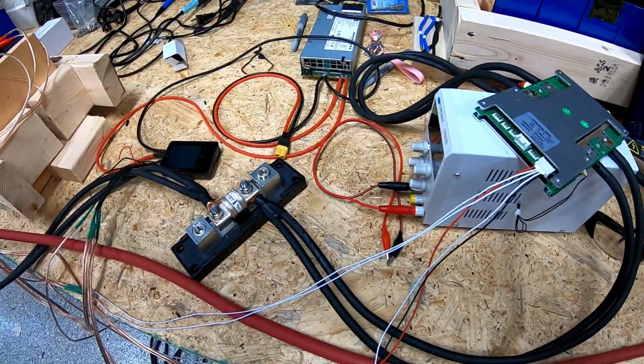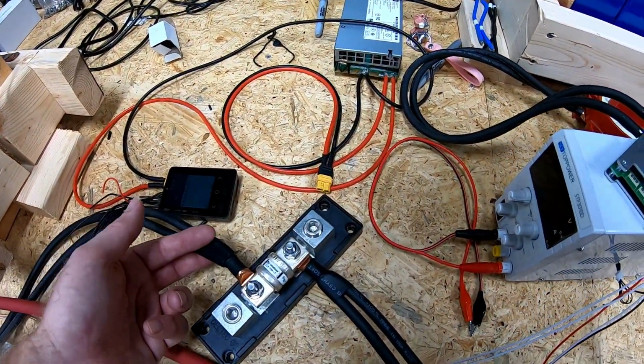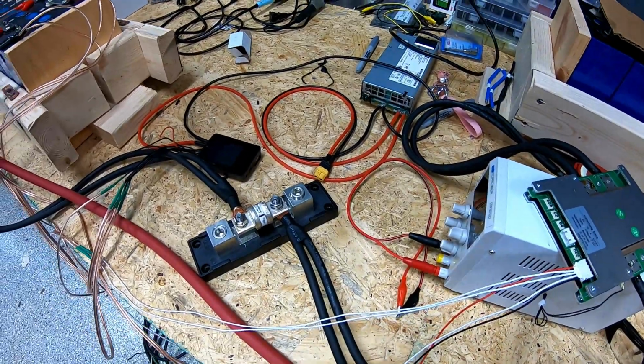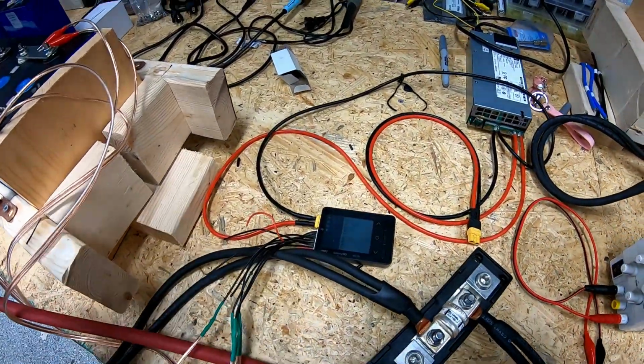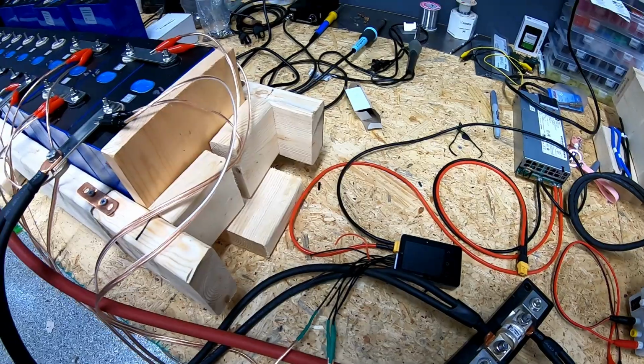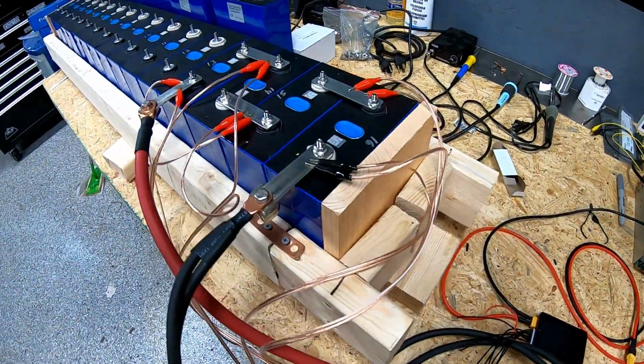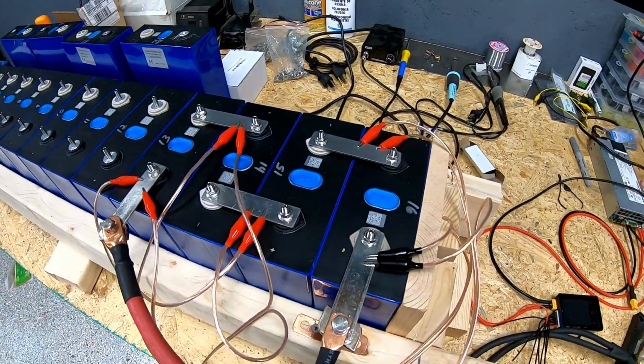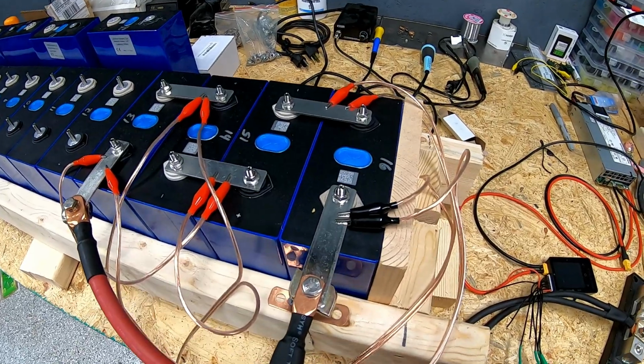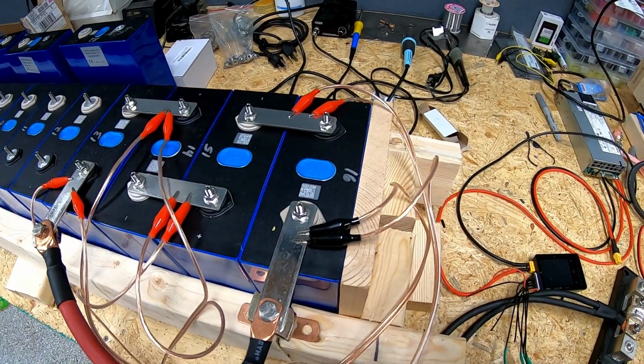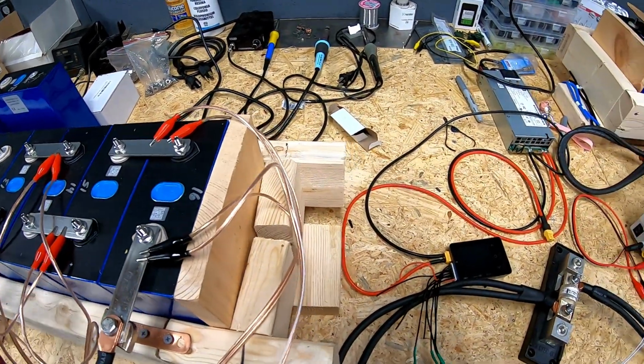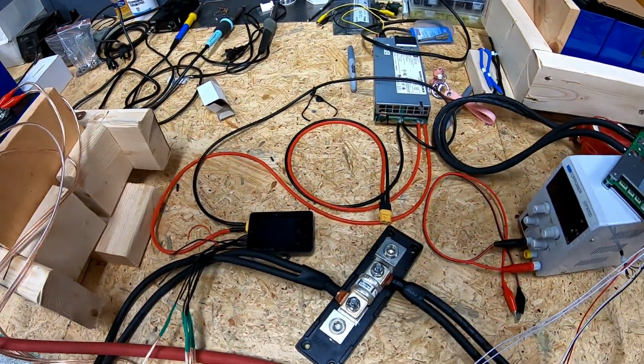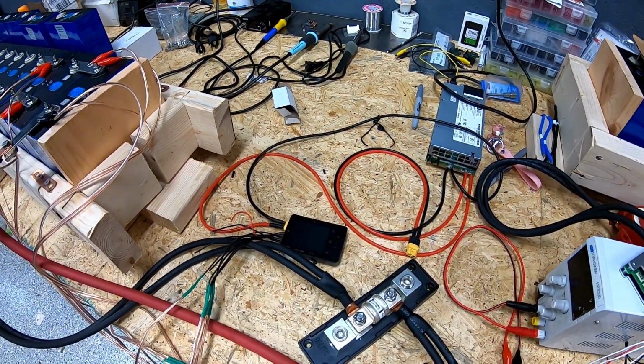Now, typically when you see these load tests done, they'll charge the pack up to a full 3.65 volts, run a complete cycle, and generally if the cells are new, what you want to see is the full 280 amp hours they're rated for. A lot of times, even newer cells, you'll see slightly above that. And then as they cycle a couple of times and break in, they'll come down to that 280 amp hour value.